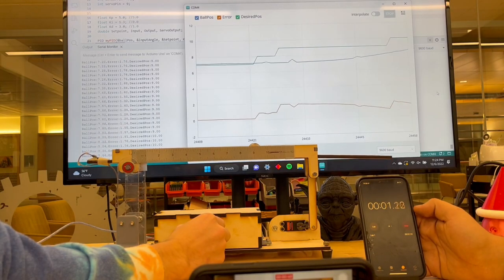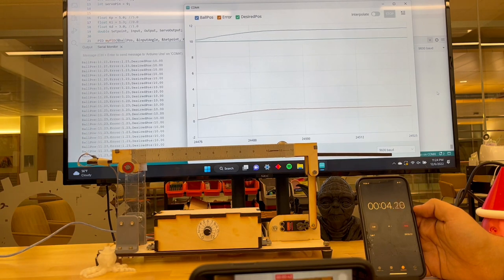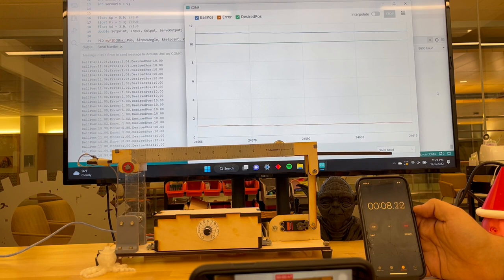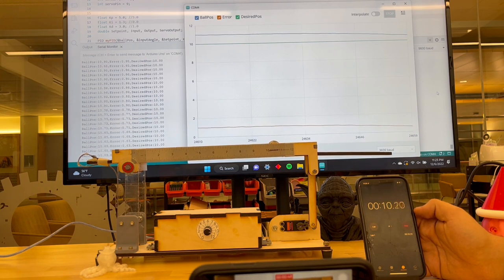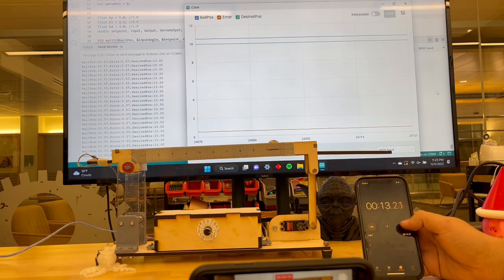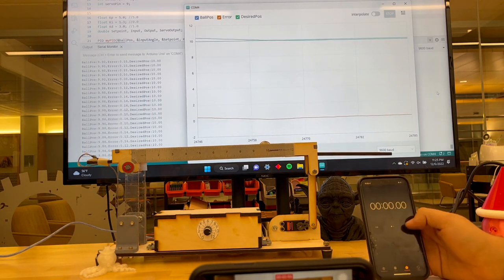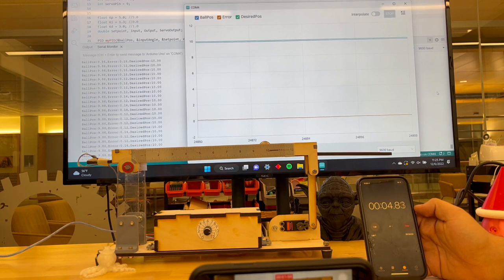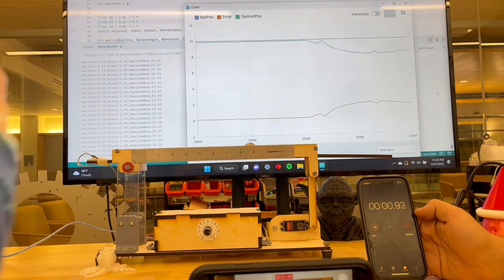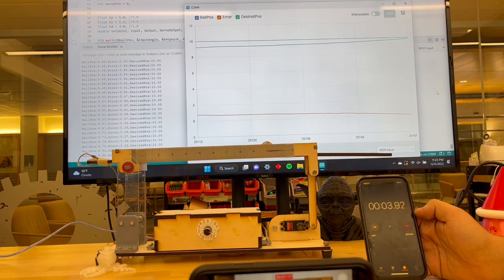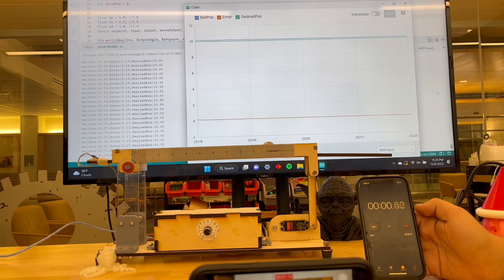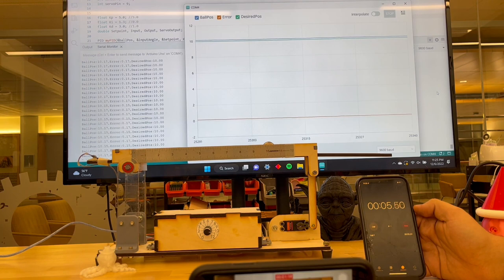Now we will look at a bit of our test from 7 inches to 10 inches. As you can see, we changed the dial over to 10, and it's going to start slowly zeroing in on the correct value. And as you can see that took about 15 seconds, so now we're going to let it sit for 10 seconds. And then at the end of the 10 seconds we displace it, and it very quickly comes back to 10 inches in about 5 seconds. And then we will continue to let it sit for another 10 seconds.